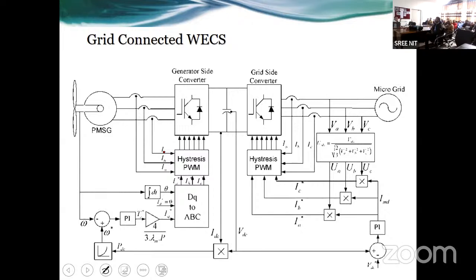Getting it? And on the grid side, as I have told you, you must maintain the DC link voltage constant at any cost. So the reference DC voltage and the actual DC voltage are given to a PI, and it gives you the amount of active power exchange which must be required under the given circumstances. Because on the one side you are generating power, and on the other side you have to maintain the DC link constant under the generated power. So it gives you an idea of how much active power must be injected in the form of current. Because active power injection means you only need to control the current, the voltage is already there.